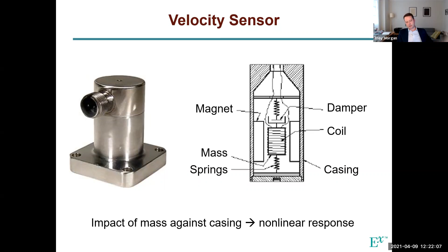The sequence of events is this: the earthquake occurs, and it has 3 directions of shaking. It's not just vertical, but the vertical motion is what we're interested in since that's what the vibration monitor measures. Motion propagates up through the generator into the transducer, which spits out a voltage as a result. That voltage then goes to a vibration monitor, which sends a signal to what's called an Agastat relay.